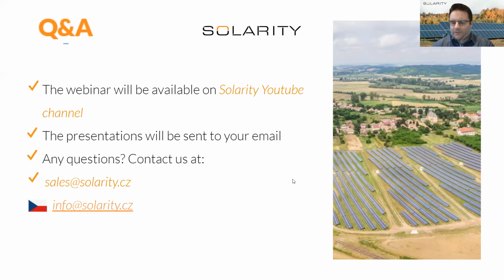Thank you. We also have a question regarding communication, I assume also for Mr. Kotrba, about Modbus communication. I assume the question is whether it's possible to communicate through the Modbus protocol over Ethernet. From my experience I'd say yes, but please confirm. There is available Modbus RTU or Modbus TCP. Modbus RTU is designed for communication with a smart meter, and Modbus TCP allows communication over Ethernet.